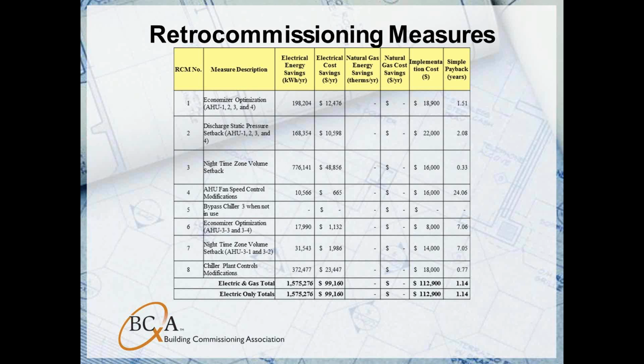But it's important to note that this building has electric reheats on the VAV boxes. When you have electric reheats, you have to be cognizant of the minimum airflow that's required for those reheats to operate properly. So that's just something to keep in mind if this is a measure that you're recommending.